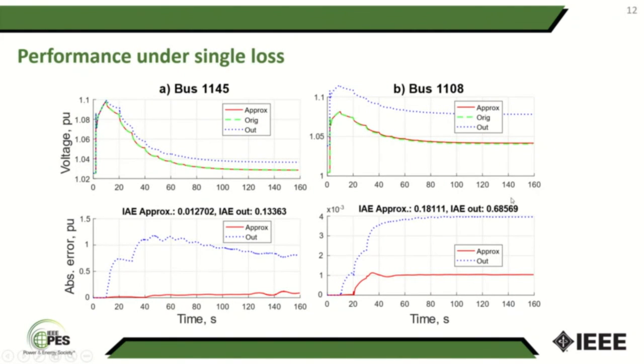And now here we have the performance of the system at two different buses for single losses. The 1145 bus is at the tail end of a feeder, and the 1108 is located at a much stronger point, near the substation. We applied a severe disturbance in the transmission grid at 1 second of simulation. Notice how the controller is able to correct the voltage values and move them to the acceptable bands. Notice how neglecting the control of the lost bus, that would be the blue dotted line, deteriorates the performance of the controller. On the other hand, if the lost measurement is approximated with pseudo measurements of the algorithm, the performance of the controller is practically the same as if all the measurements were available.